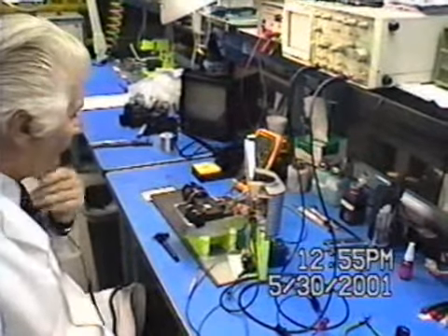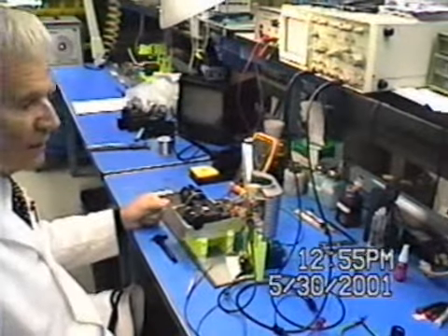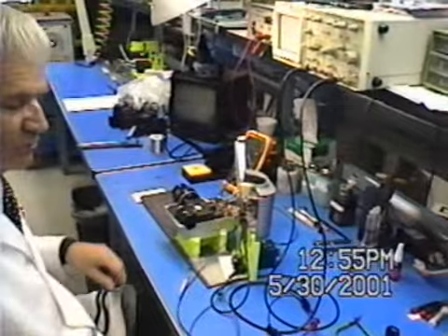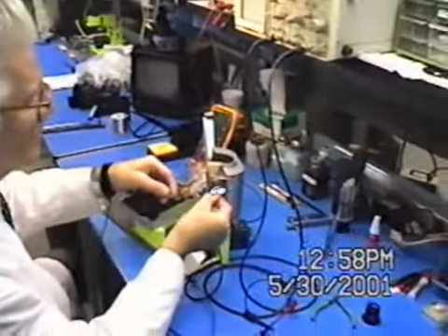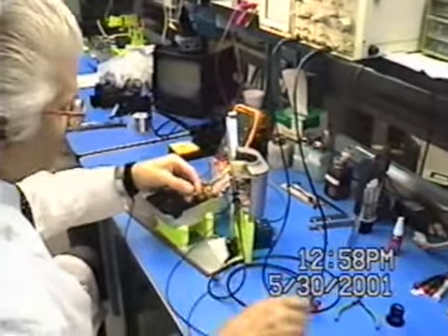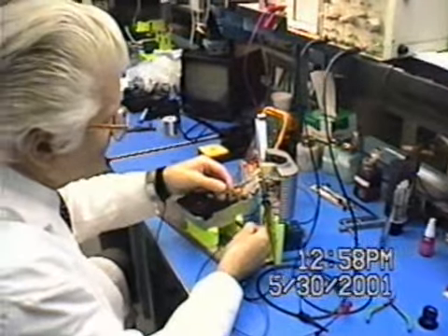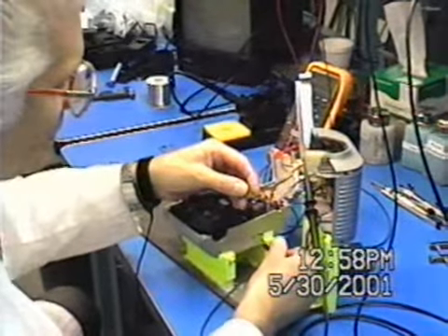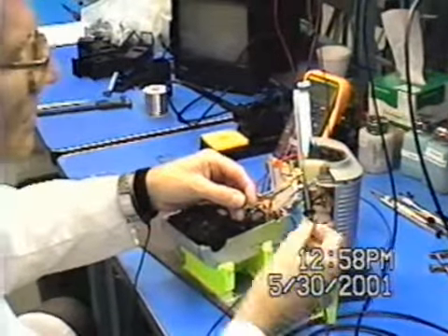Okay. Next thing is the emissivity. Okay. We can take the furnace away. We don't need that furnace anymore. Changing that resistor so drastically, it changed everything, including the zero. So the zero is too low. Now I'm going to adjust. This is the null adjustment for emissivity.